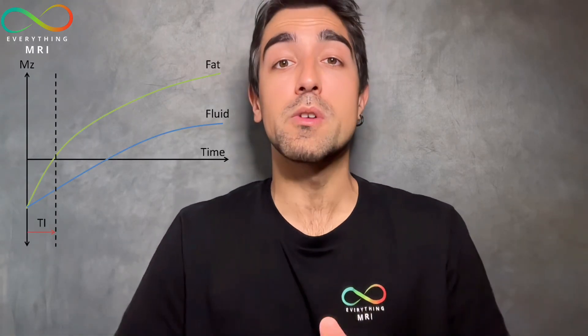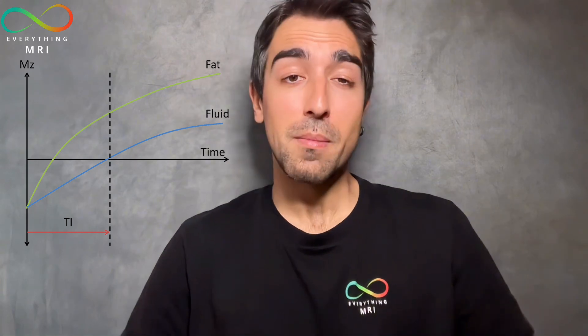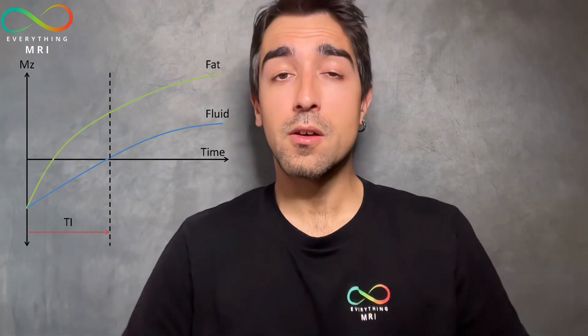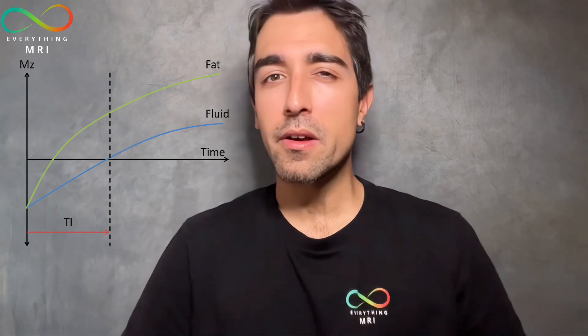Is your goal to suppress fat? Choose a STIR sequence with a short TI, usually around 150 ms at 1.5 Tesla. Is your aim instead to suppress fluids like the CSF? That's where the FLAIR sequence shines. The CSF has a much longer T1 than fat, requiring a longer inversion time, usually around 2500 ms at 1.5T. Exact TI values might vary slightly between scanners and radiologists' preferences, so do not panic if your protocols are saved with slightly different TI values.